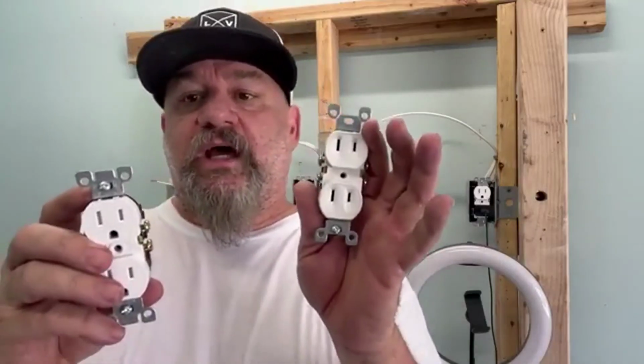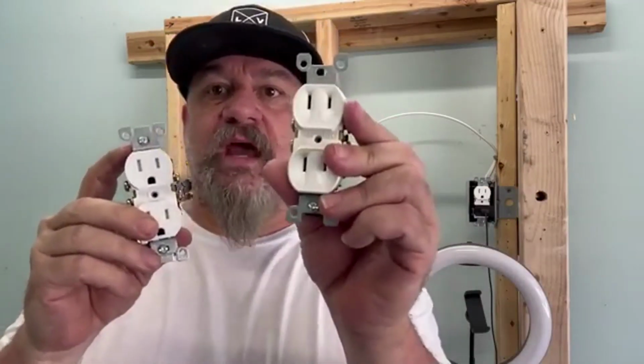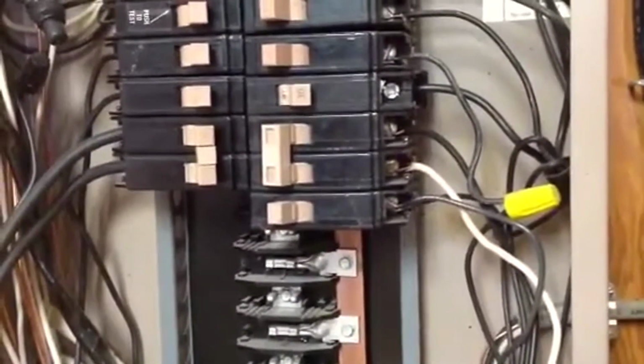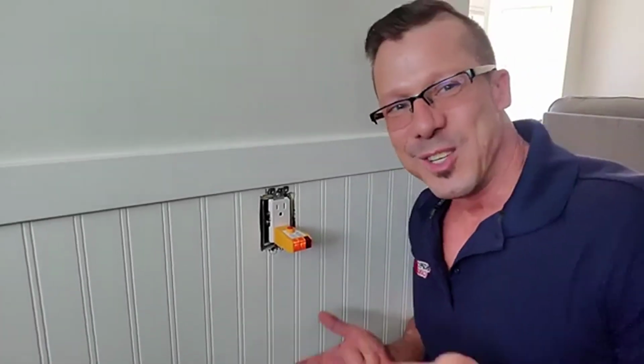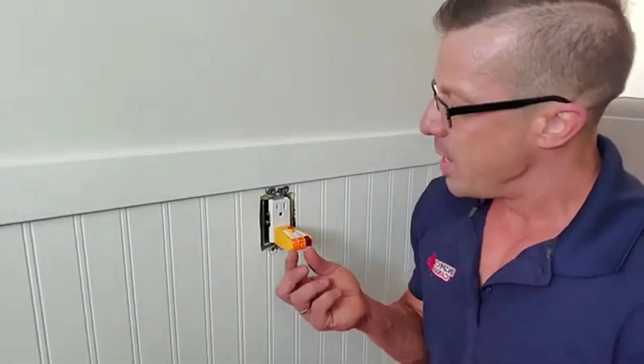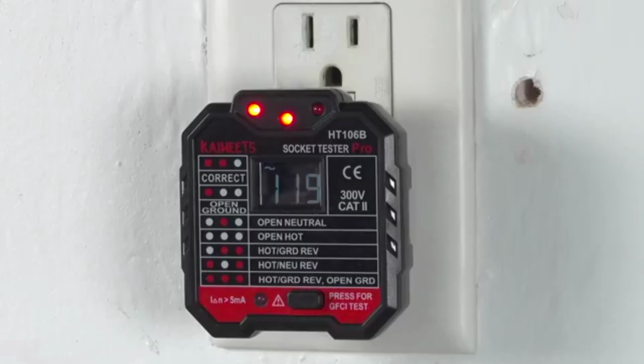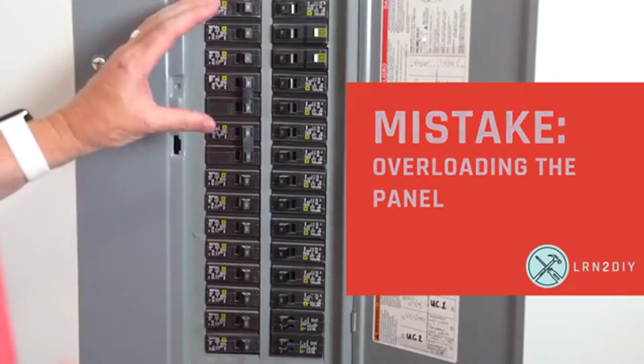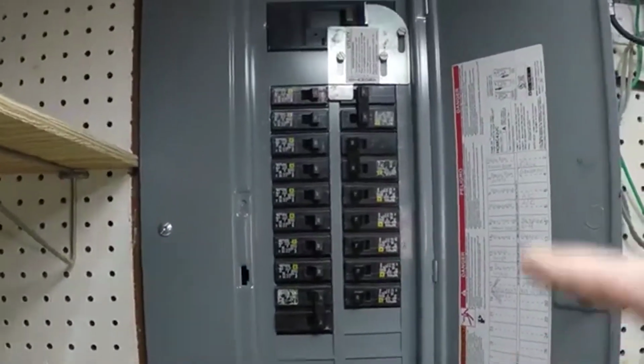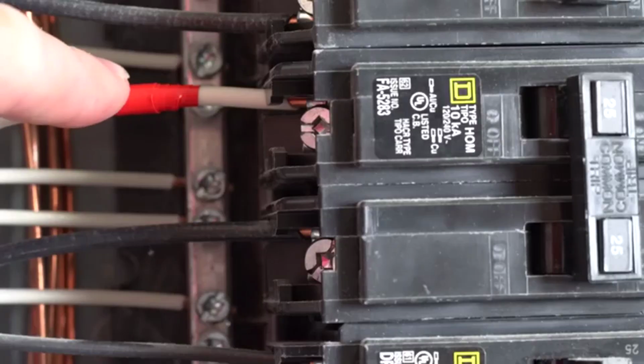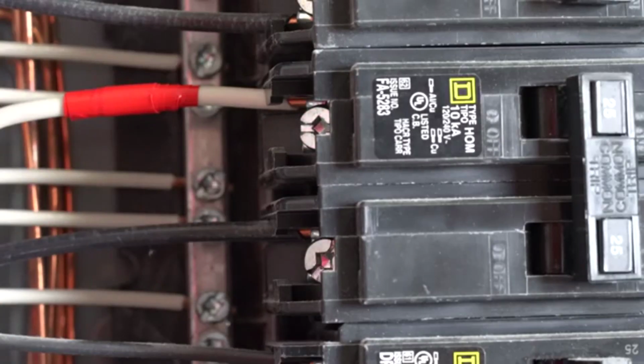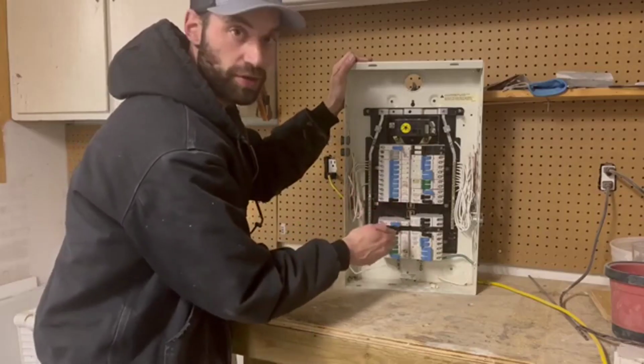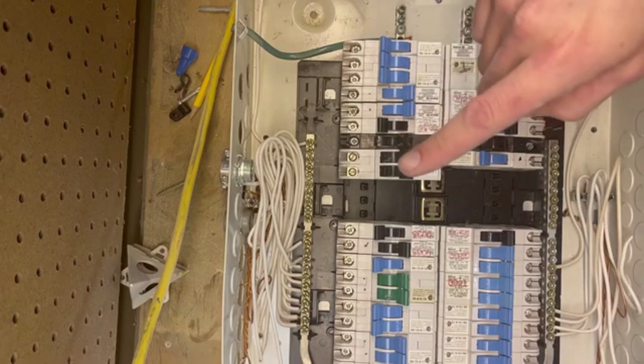The second thing that shows up constantly is electrical. And I'm not just talking about old knob and tube wiring in a 100-year-old house. I'm talking about problems in relatively modern homes too. Double-tapped breakers, which is where two wires are connected to a single breaker slot that's only rated for one wire. Missing GFCI outlets in the kitchen, bathrooms, garage, and exterior. Reversed polarity on outlets. An electrical panel that's been recalled. Certain brands have been subject to safety recalls for decades, and they're still sitting in houses all over this country right now. Federal Pacific and Zinsco panels are the two big ones. If your home has one of those, buyers are going to see that in the report, and their insurance company may not even want to cover the home until it's replaced.